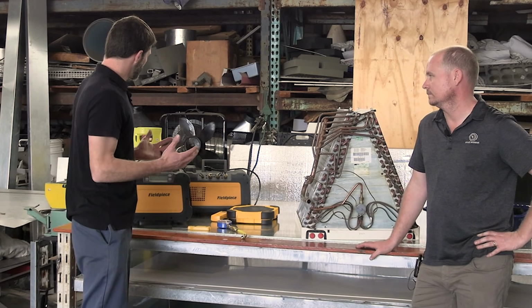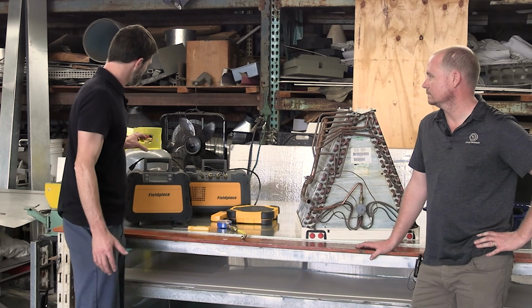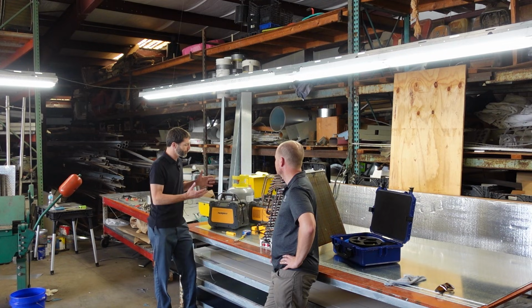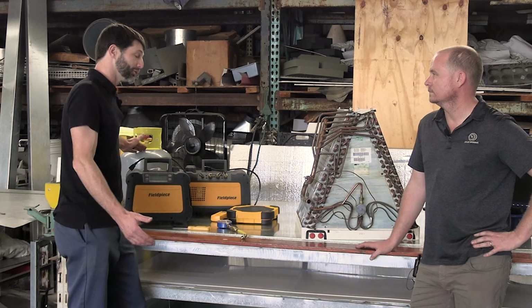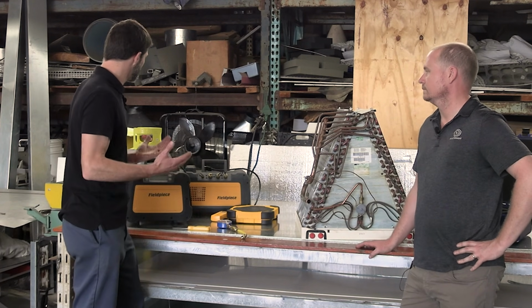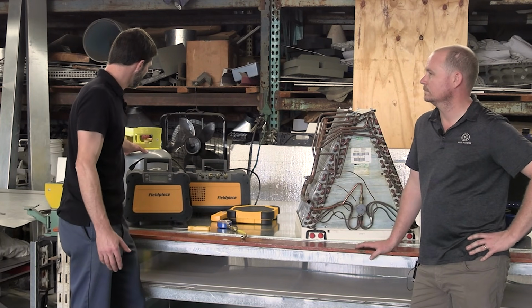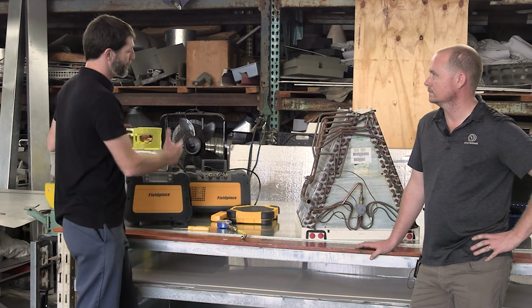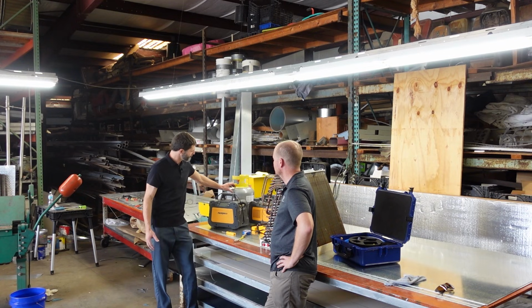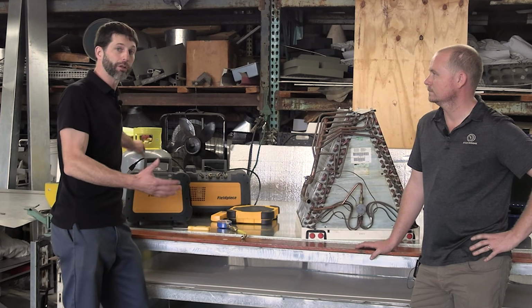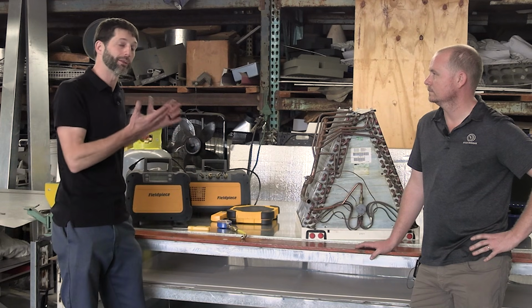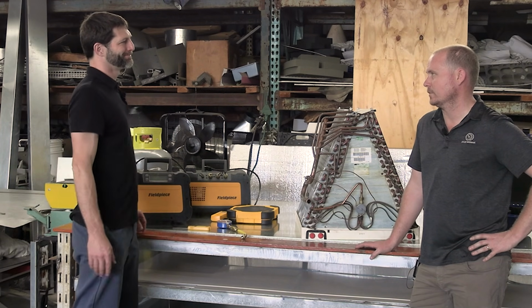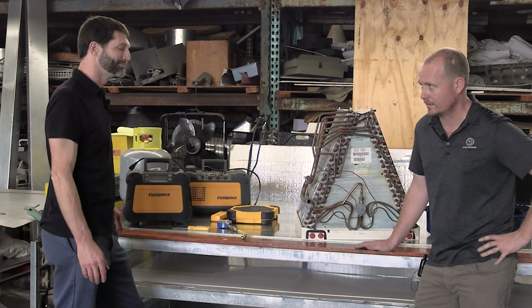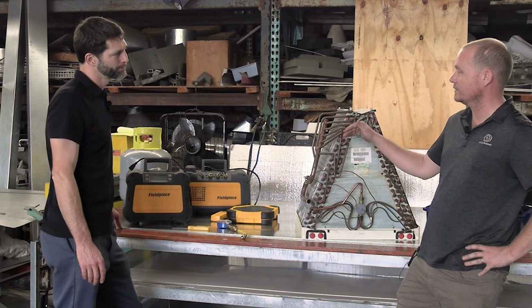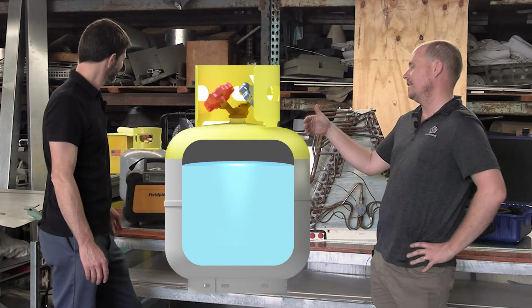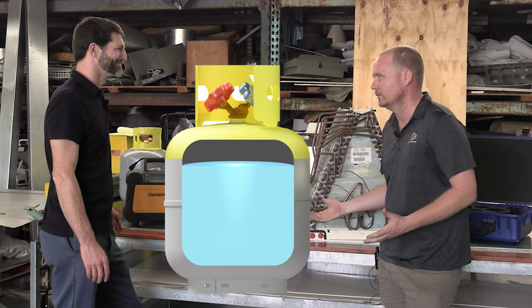But one thing I just want to make sure that you're aware of is to make sure that also the tank is not too full and you're trying to basically overfill it, and that would potentially be a dangerous situation, especially when the surrounding air temperature is high, and basically you have the expansion of the refrigerant, and you have no room for the vapor within the tank. Yeah, and that's what we call hydrostatic pressure. So the goal would be, even in a worst case scenario, to make sure that you don't fill the tank to over 80%.